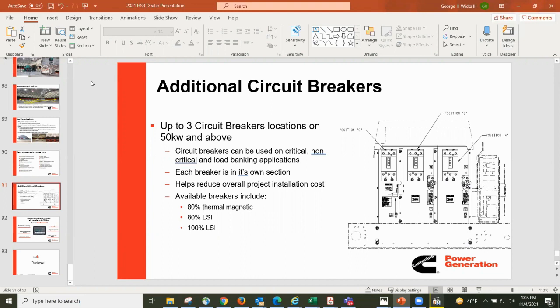Okay, because I noticed, and knew it had to be something else besides that circuit breaker, as far as the load—I even witnessed load bank testing, where they load the generator up to its full capacity just to see if any other device would shut that breaker down before it reached full capacity. So I just wanted to get a clear understanding of that inherent design and what it really means. I know it's a part of the generator that cannot be changed, but what exactly does that mean as far as the National Electric Code? That was my question.